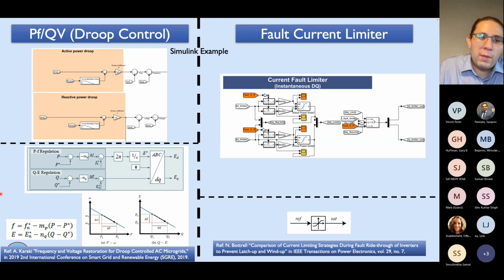On the upper figure, we have the Simulink control implemented, and in the bottom, I have a reference. So we can see that the frequency and the voltage value in the reference frame are shown as F and E star. P and Q are the output active and reactive power of the inverter. The F and E without the star are the nominal angular frequency and the output voltage amplitude. We do have two values, M and N, which are the proportional frequency droop coefficient, which is M, and N is the voltage droop coefficient. They are utilized for sharing the load between different inverters that have the same type of construction, like they have droop control enabled.